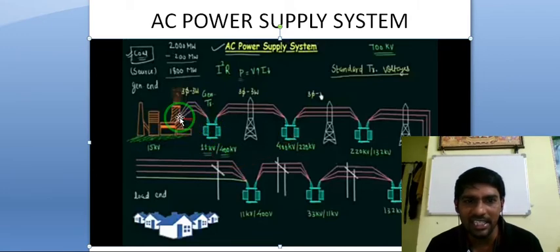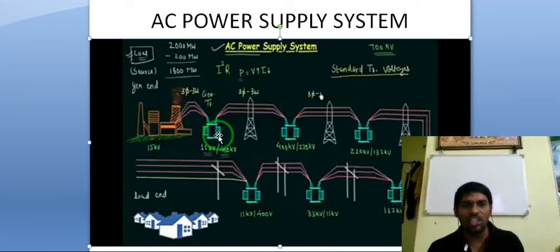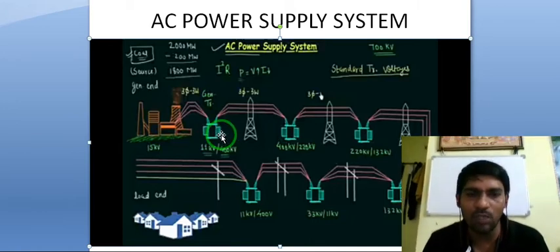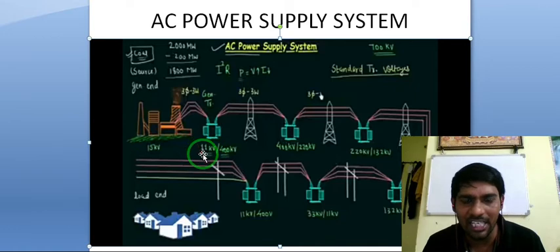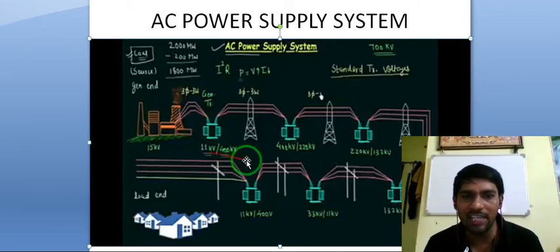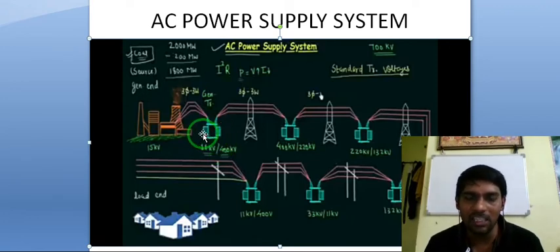Nearby the generating station, we use one transformer, that is called one substation. By this substation, we can step up the voltage level. The generated voltage is 11 kV. We are assuming that the 11 kV is stepped up to 400 kV by this transformer, without disturbing the power. Whatever power is generated by this generating station can be transferred from primary to secondary. We can step up the voltage without disturbing the power as well as the frequency. Whatever power is on the primary, the same power appears on the secondary side, so we are not disturbing the power component here.